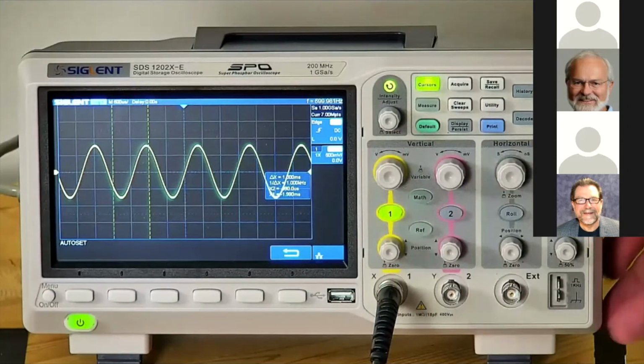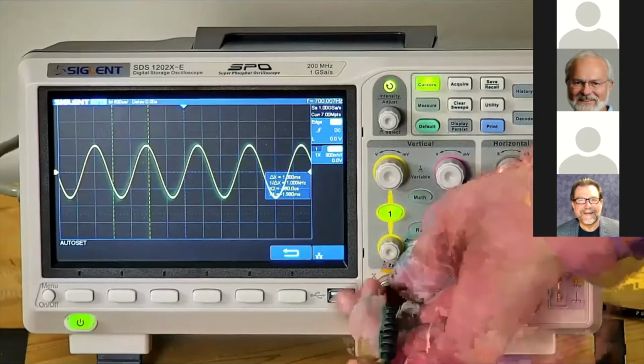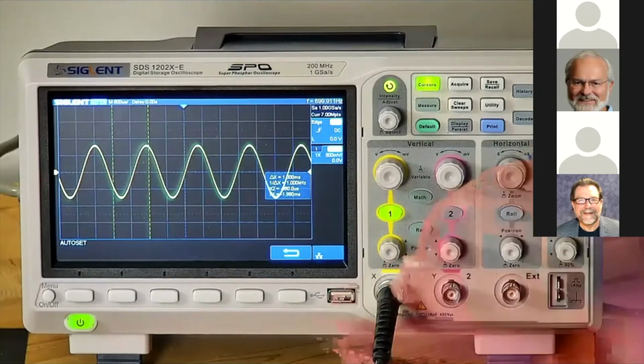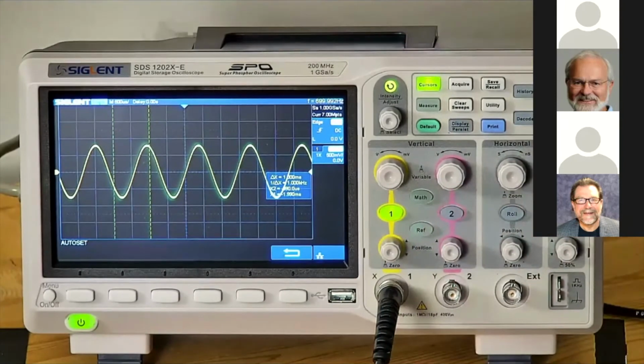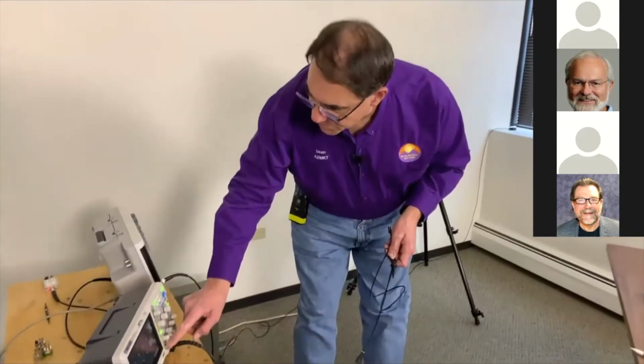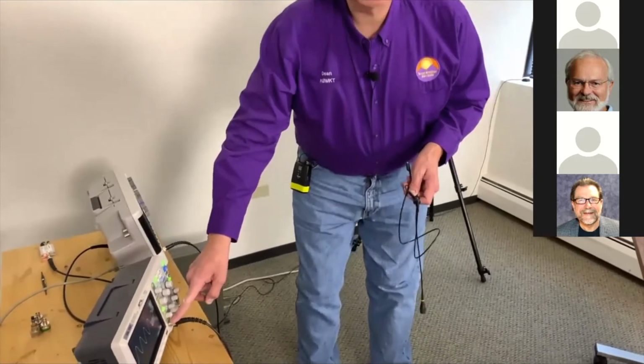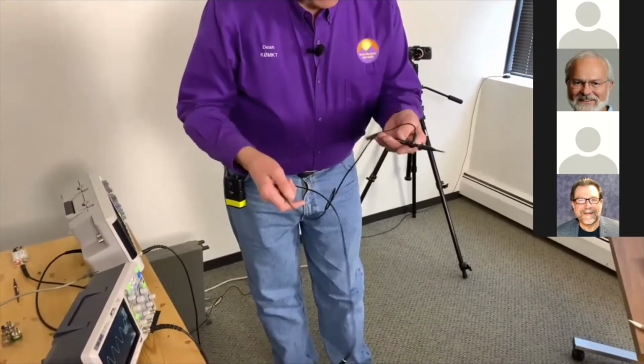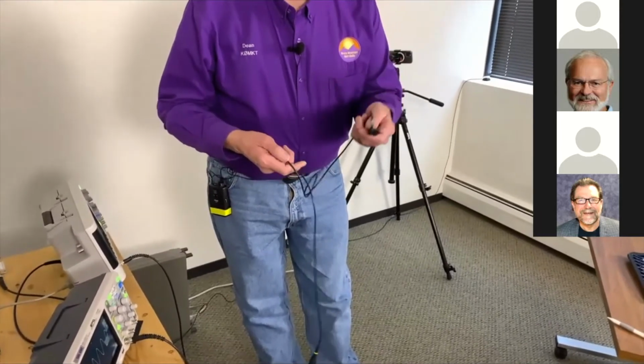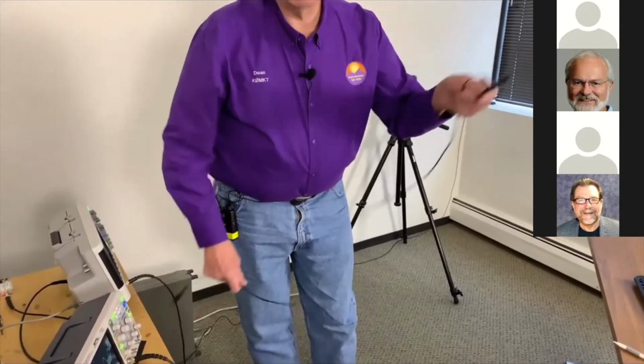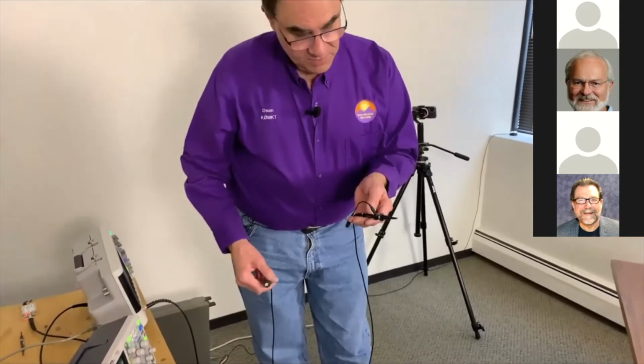But that is very important to know what the max voltage limit is that you're looking at. So that's one of the reasons why the probes are like a 10-to-1 probe, for example. The input range might be 20 volts. That might be the maximum. But with a 10-to-1 probe, we can look at 200 volts, because 200 volts divided down gives 20 volts at the output.